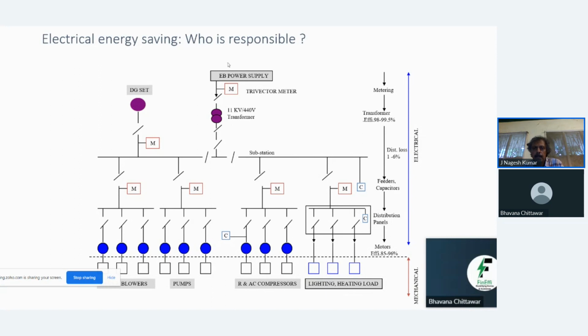We have the supply coming from the grid. This is a typical electrical single line diagram of an industrial electrical system. Power comes from the grid through a transformer. This is the first loss that happens in industry - the transformer loss is about 1 to 1.5%. So transformer efficiency is pretty high.